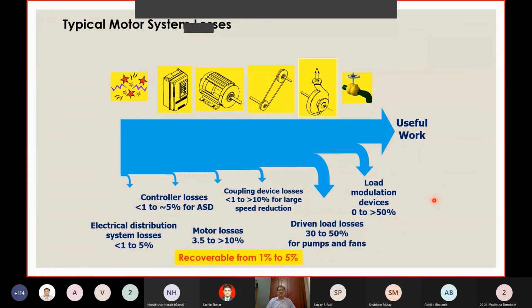So typical motor system loss in a pump. I showed you a fan. Similarly, in a pump, there are so many losses because of the drivetrain, complete drivetrain, the method of starting, motor itself, belt pulley, the valve, friction losses in the delivery side, and all those things. So typically in a motor, only 1 to 5% can be recovered in a pumping system. But if you undertake replacement of pump or partly replacing the impeller or internal coating and things like that, there's a lot of losses which can be recovered. As much as 30 to 50% reduction can be shown.